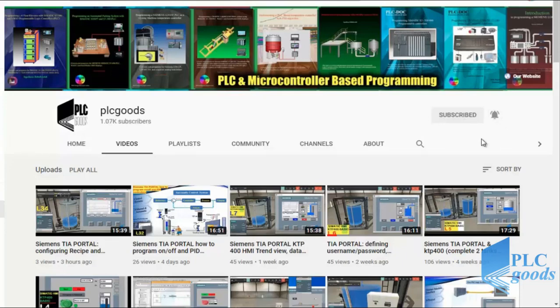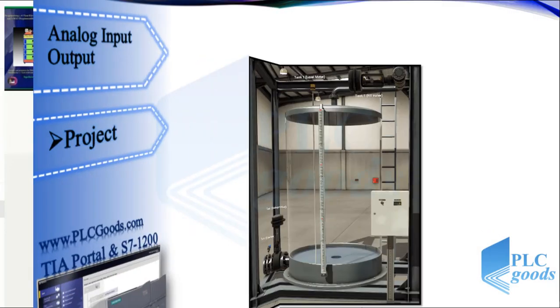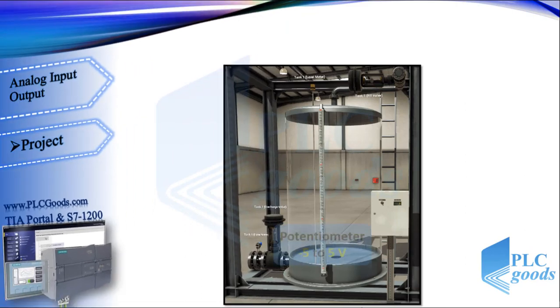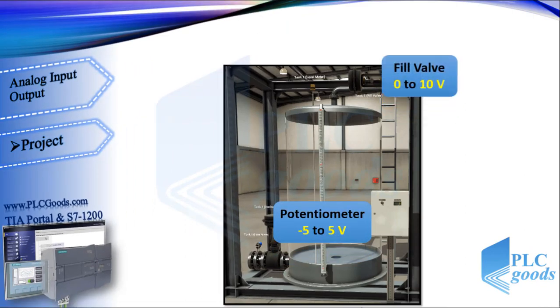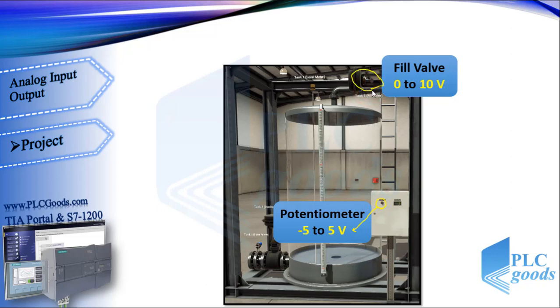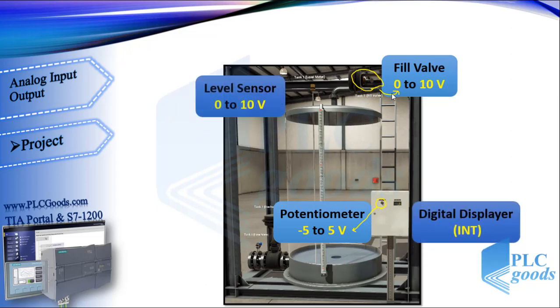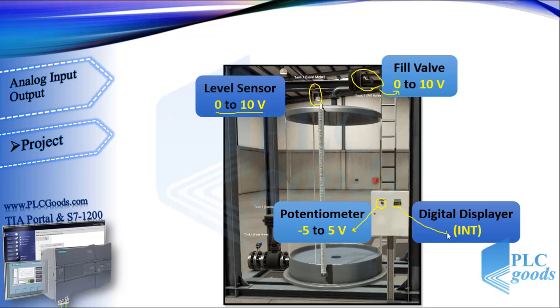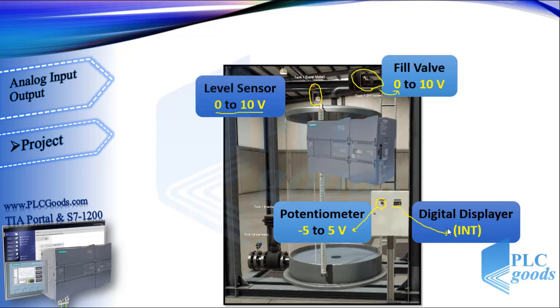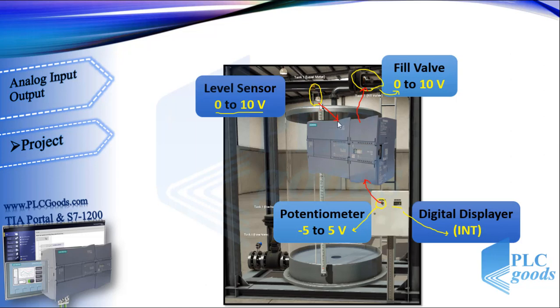All right, this is the tank which has been used before. Here are a potentiometer which give us a voltage between minus 5 to 5 volt and an electrical valve which can be controlled with a voltage between 0 to 10 volt. Also the tank has a level meter which give us a voltage up to 10 volt when the liquid level is 3 meter. Finally, this is a digital displayer which get and display integer numbers. All these devices are analog type. In this project we'll see how the potentiometer can send its voltage to PLC and convert that to a voltage between 0 to 10 volt to control the fill valve, and also we'll see how the PLC can get the level meter voltage and show the liquid level on the digital displayer.